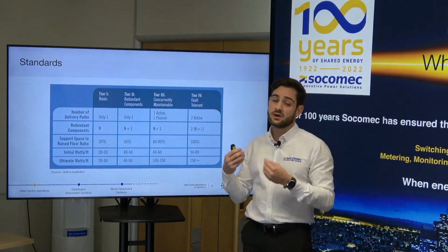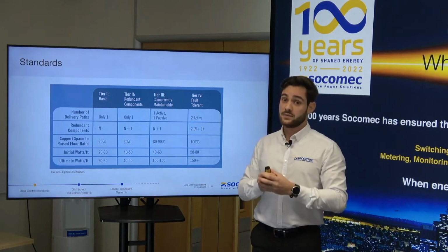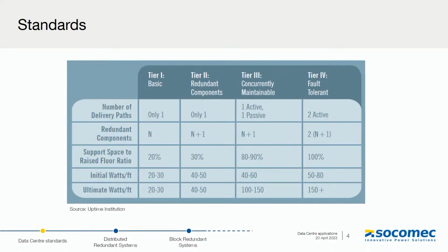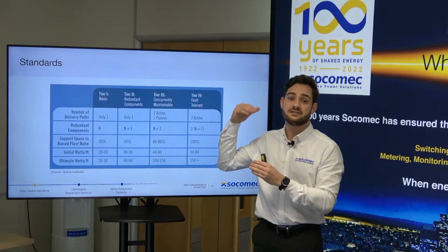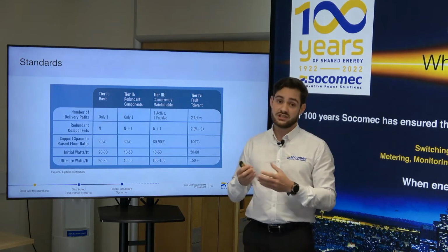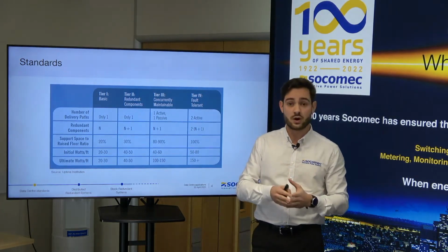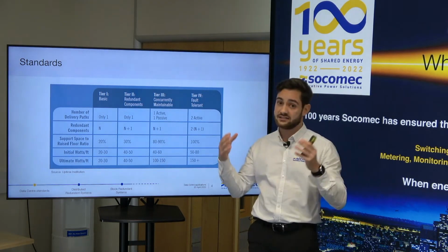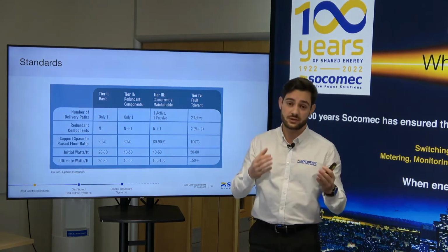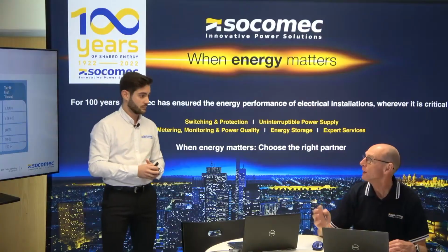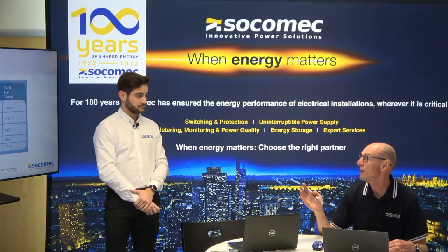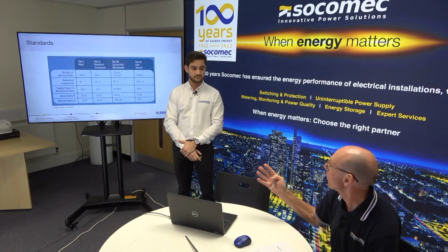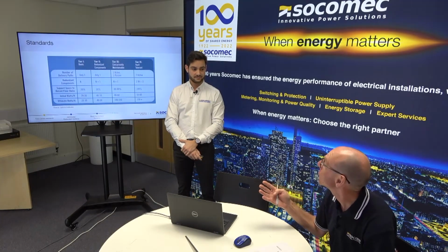Tier 3, we call it a concurrently maintainable data center because we have two paths of power. One active path and one passive path, which allow for maintenance purposes. And then tier 4, which is a fault-tolerant data center, which is the highest in the data center industry, which is called 2N+1 data center. Where you would get two active paths and redundancy on each path. So realistically, if you're thinking of a data center, you are really thinking about tier 3 and tier 4, where you've got the co-location data centers or the big cloud server data centers. It's really 3 and 4 that we're looking at.